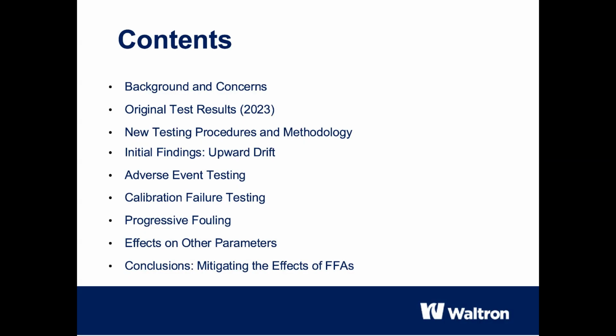We'll begin with the background and concerns that led us to conduct this research. We'll then review our original 2023 test results and then introduce our new, more detailed test procedures. We'll analyze the results of these new tests, including initial upward drift, response to simulated incidents, and calibration failure tests, which highlight the critical issue of progressive electrode fouling.